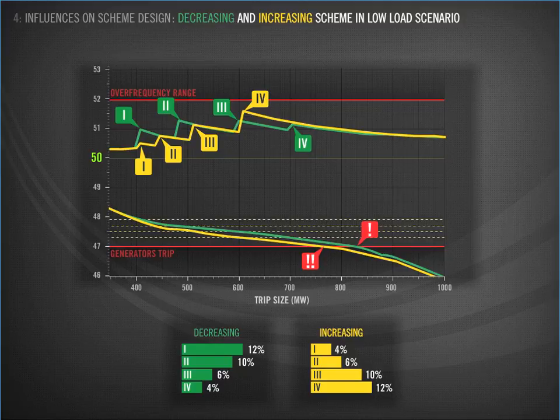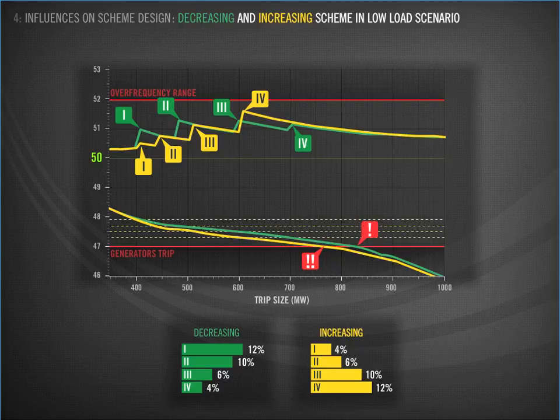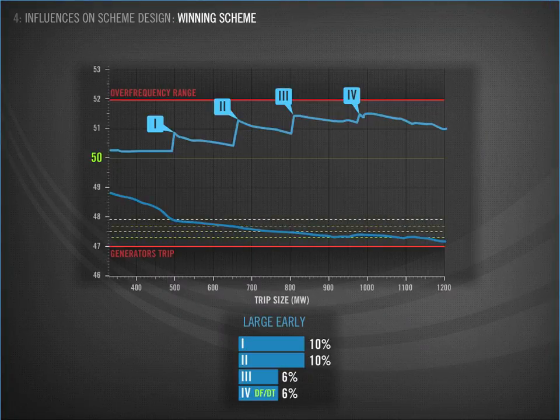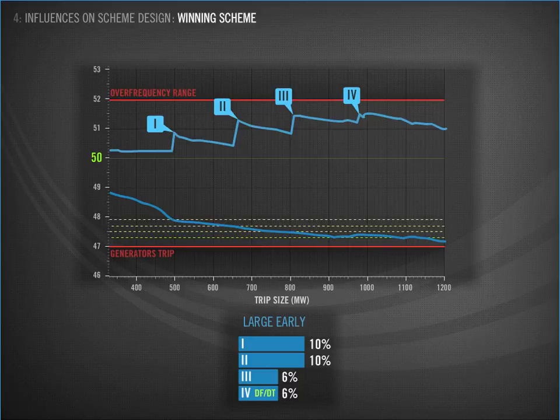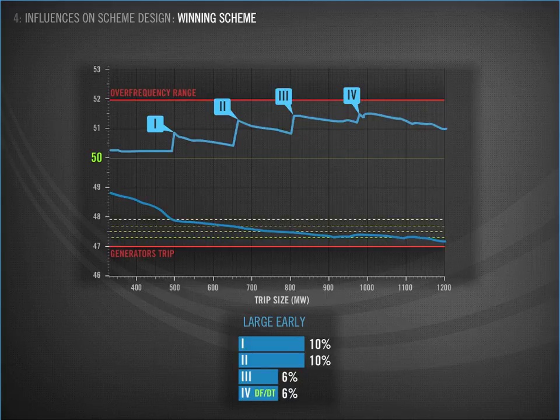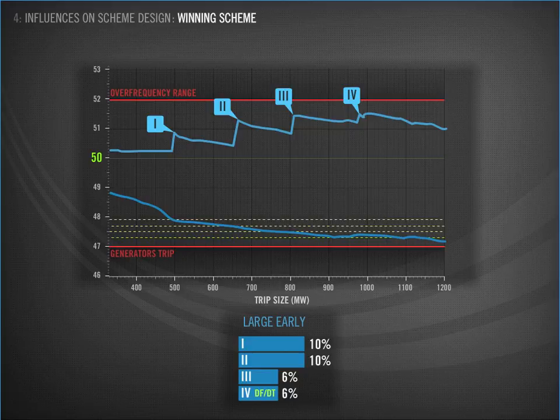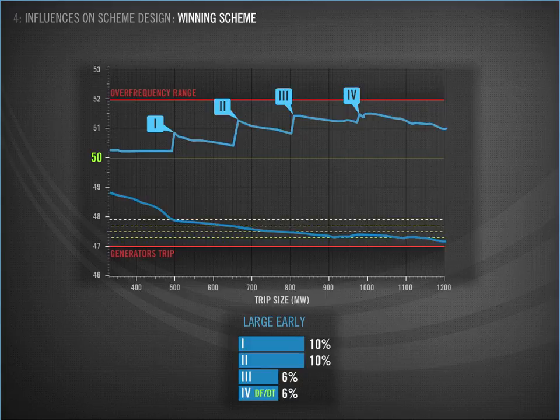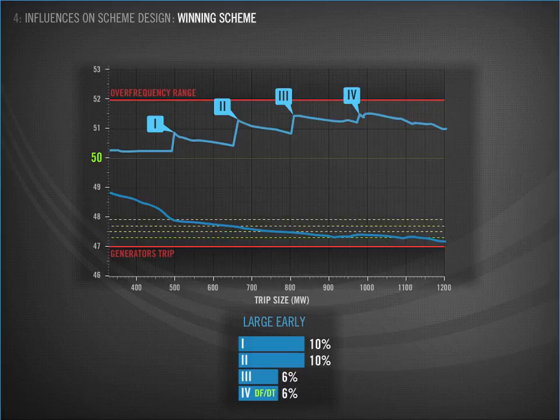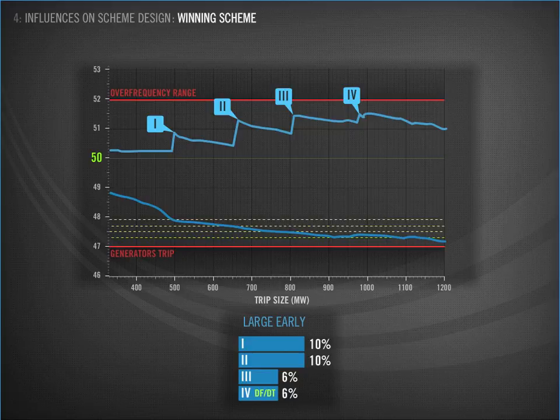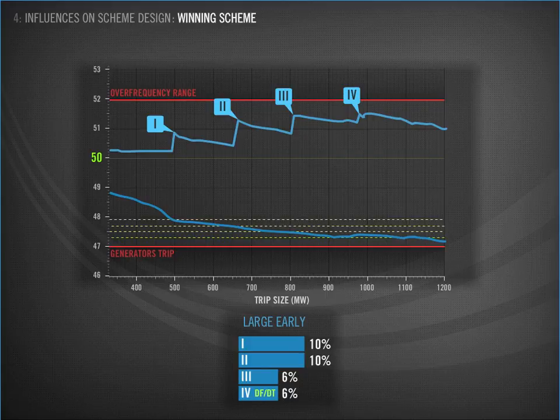This sawtooth analysis allowed us to assess the different scheme designs we discussed earlier. We could assess each scheme based on the points where it maintains the frequency between 47 and 52 Hz. Here's the winning scheme. Four blocks of 10, 10, 6 and 6%. You'll notice that we have included DFDT on block four. Adding DFDT to the last block of the strongest performing scheme gives us an additional weapon to deal with events where the frequency is falling fast, for those large events where it is expected that all four AWFLS blocks may be required. You will recall that when DFDT triggers, it increases the minimum frequency and gives us more distance from the under-frequency limit. Although no scheme can give coverage for every event, this winning scheme allows us to stay within 47 to 52 Hz for a wider range of disturbances. This was the strongest performing under-frequency scheme.